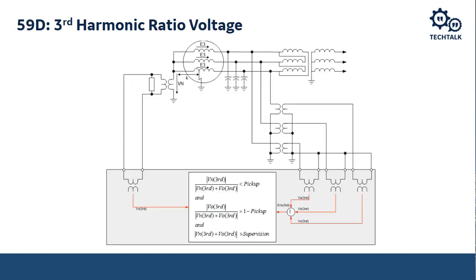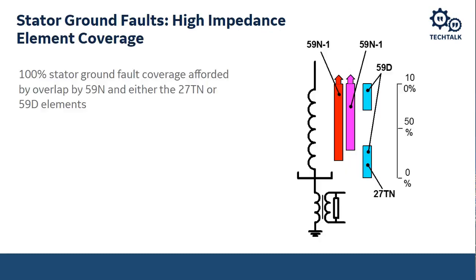Whereas with the 59D element, if you use the third harmonic ratio voltage, we're basically not subjected to those pockets. We might not be able to trip for a ground fault because there's no third harmonic voltage generated, but we're not going to misdetect the ground fault either. So it's more secure. Basically, the voltage type protection for a high impedance grounded generator is a combination of the 59N, the 59D, and the 27TN to give us 100% overlapping coverage for ground faults within the generator.